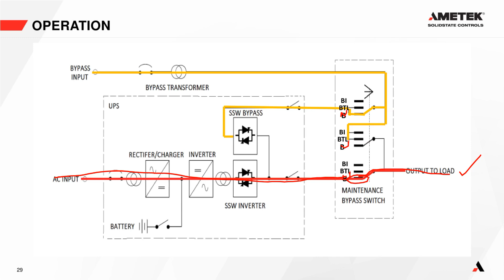But our bypass supply is allowed to go down through this contact here, which is the normal contact, out into our bypass static switch at this point here. Okay, so it's ready and available. So if somebody wants to press the bypass to load button, or if the inverter fails, we can turn the bypass static switch on and allow power to flow through this way if we need to. Okay, so that is the normal position of the maintenance bypass switch.